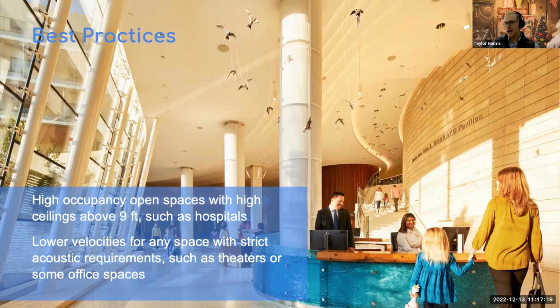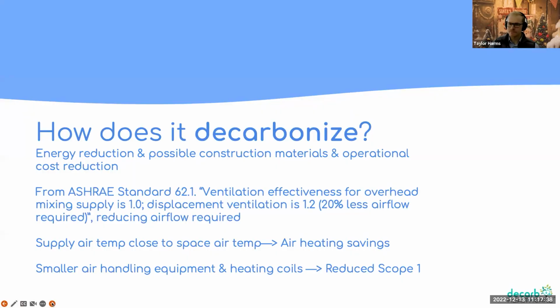Best practices, displacement ventilation works best in high occupancy spaces with really high ceilings so that you can really get the stratification effect of the clean air at the bottom and the contaminated air higher up. Displacement ventilation decarbonizes by reducing energy at both the boiler and the chiller. And because there is lower airflow required, this opens up the possibility for using smaller ductwork as well, which leads to lower construction and materials costs.